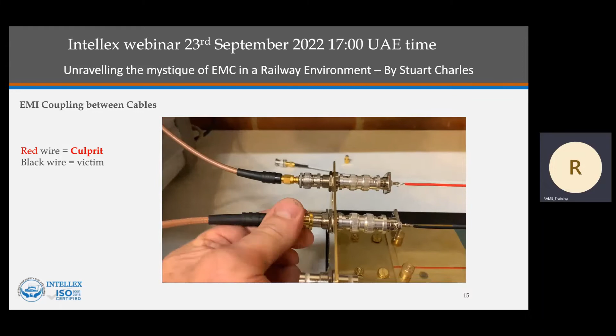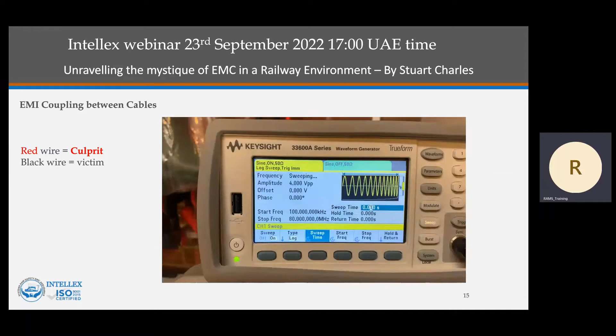I'm now going to connect the signal wire so we can get a signal from the black wire, and let's look at the screen. That's a spectrum showing a number of frequencies. As the signal generator steps in frequency, the spectrum analyzer, which is sweeping, captures each frequency.